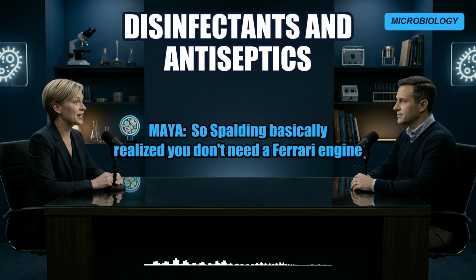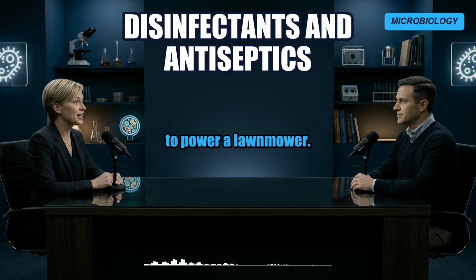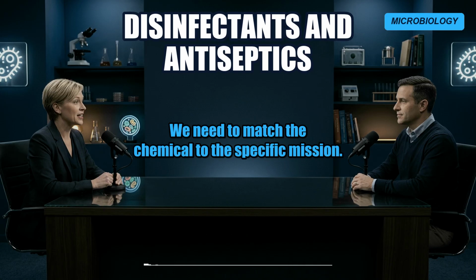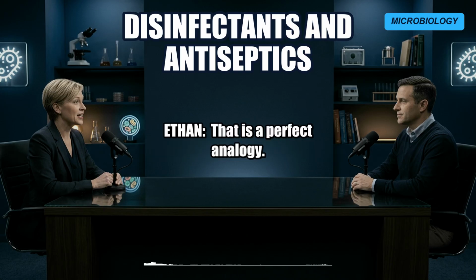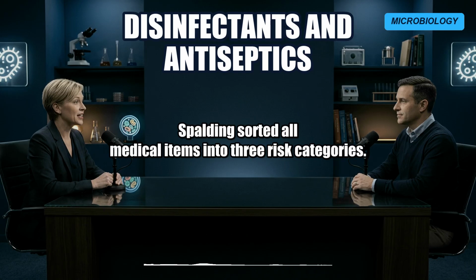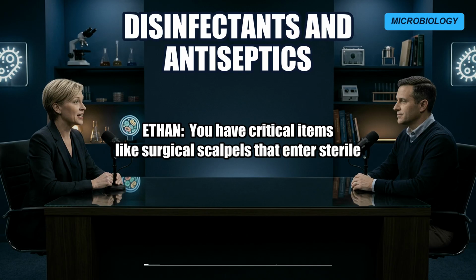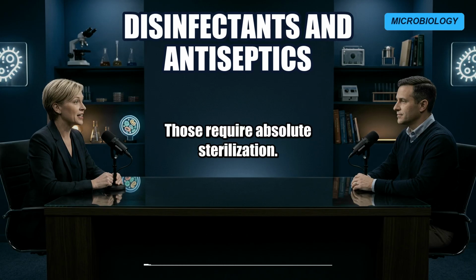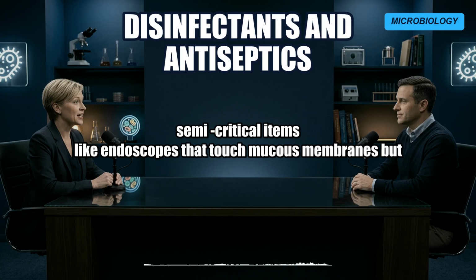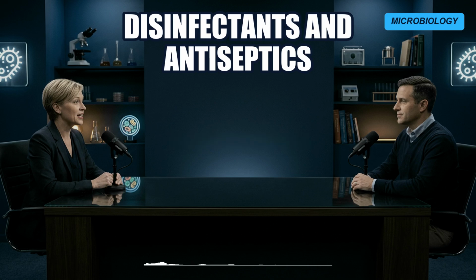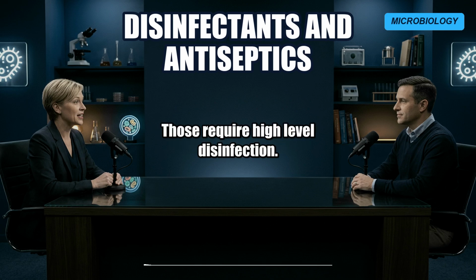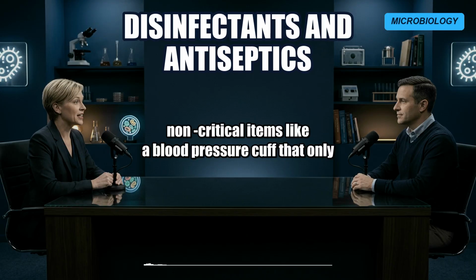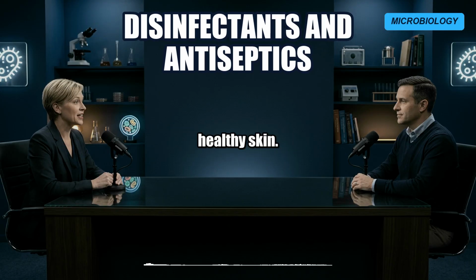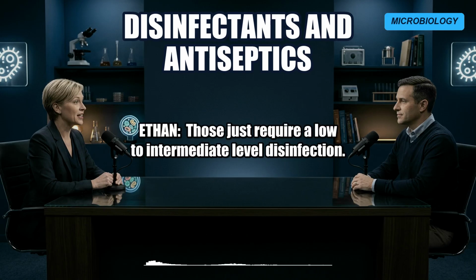So Spaulding basically realized you don't need a Ferrari engine to power a lawnmower. We need to match the chemical to the specific mission. That is a perfect analogy. Spaulding sorted all medical items into 3 risk categories. Okay. You have critical items, like surgical scalpels that enter sterile tissue or the bloodstream. Those require absolute sterilization. Right, obviously. Then semi-critical items, like endoscopes that touch mucous membranes but don't penetrate tissue. Those require high-level disinfection. And finally, non-critical items, like a blood pressure cuff that only touches intact, healthy skin. Yeah. Those just require low to intermediate level disinfection.